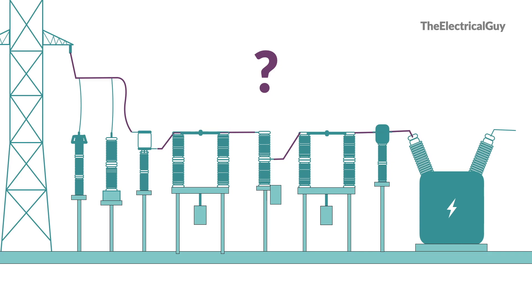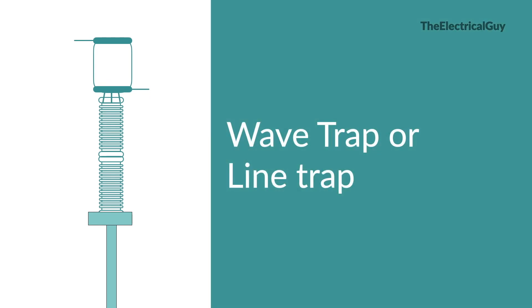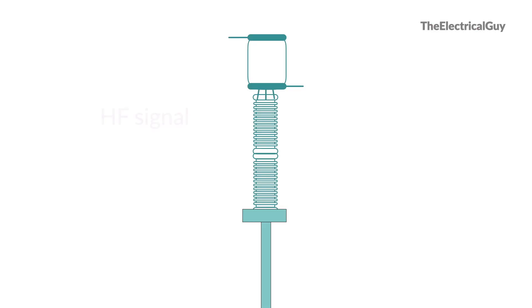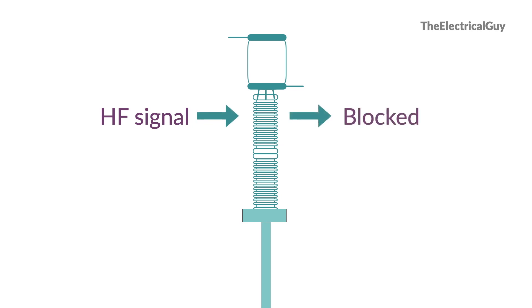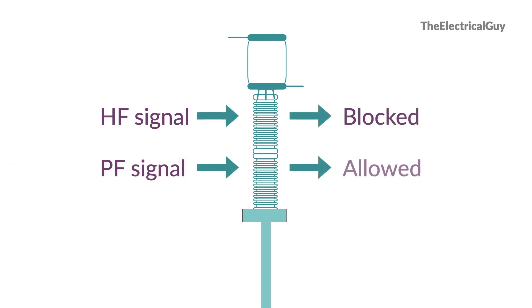And hence we must avoid these high frequency signals entering other substation equipment. That's when line trap or wave trap comes into picture. The function of a wave trap or line trap is to block high frequency communication signals going into the substation and only allow power frequency signal or current.